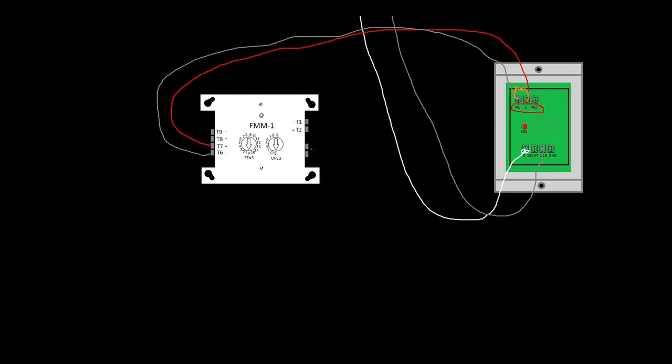Okay, so this monitor module we're going to program it not for an alarm, we don't want to set off horns if we lose power, but we'll set it for supervisory and we'll label it elevator shunt trip power monitor. And so it's going to remain clear as long as this MR101 has power.